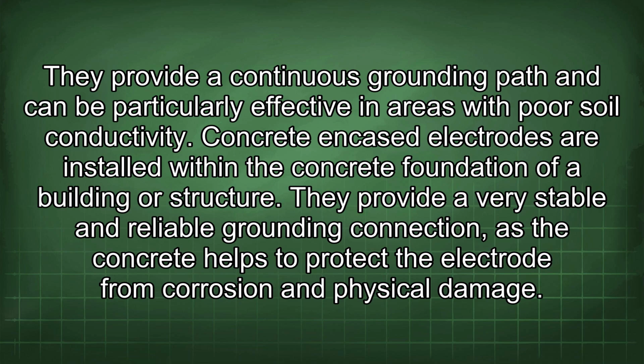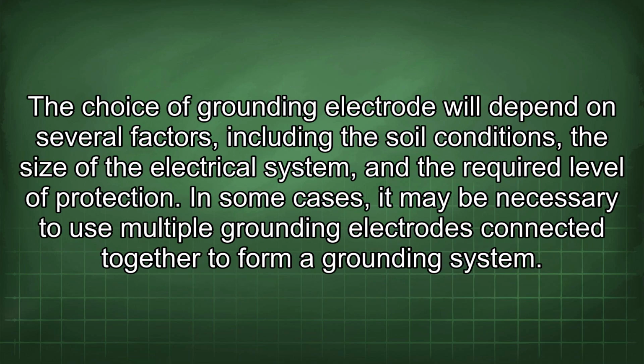Concrete encased electrodes are installed within the concrete foundation of a building or structure. They provide a very stable and reliable grounding connection, as the concrete helps to protect the electrode from corrosion and physical damage. The choice of grounding electrode will depend on several factors, including the soil conditions, the size of the electrical system, and the required level of protection. In some cases, it may be necessary to use multiple grounding electrodes connected together to form a grounding system.